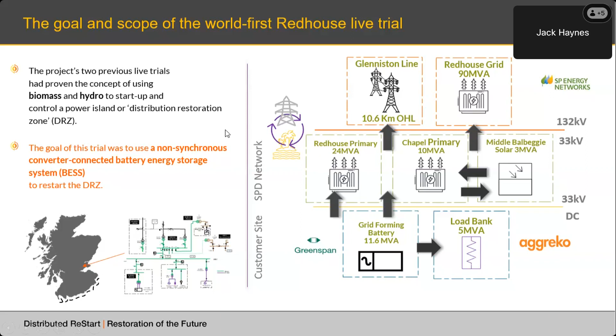And then in terms of the transmission assets that we were looking to energize, back-energized from the anchor source, we had a 90 MVA grid transformer also co-located at the Red House substation, and then also a 10.6 kilometre 132 kV line out to the neighbouring substation. So I'm pleased to communicate that the tests were really quite successful.